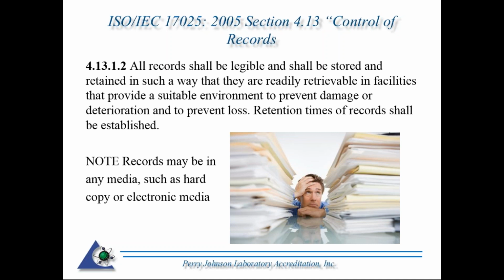So, for example, readily retrievable: if I'm doing an assessment and I ask to see a record, I generally expect to see it rather quickly. If an individual leaves the room and it's 15-20 minutes, I'm looking at my watch, I'm thinking that retrievable part may not be in place in that facility.